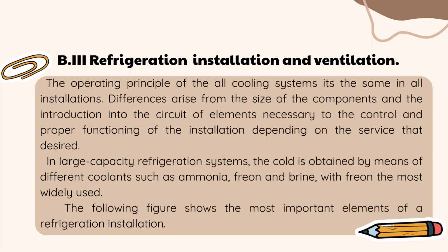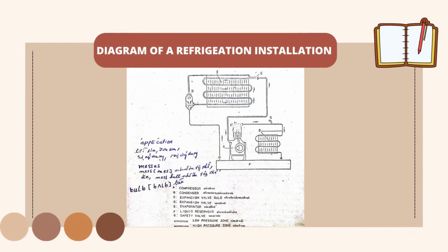The operating principle of all cooling systems is the same in all installations. Differences arise from the size of the components and the introduction into the circuit of elements necessary to the control and proper functioning of the installation depending on the service desired. In large capacity refrigeration systems, the cold is obtained by means of different coolants such as ammonia, freon and brine, with freon the most widely used. The following figure shows the most important elements of a refrigeration installation. Diagram of a refrigeration installation.